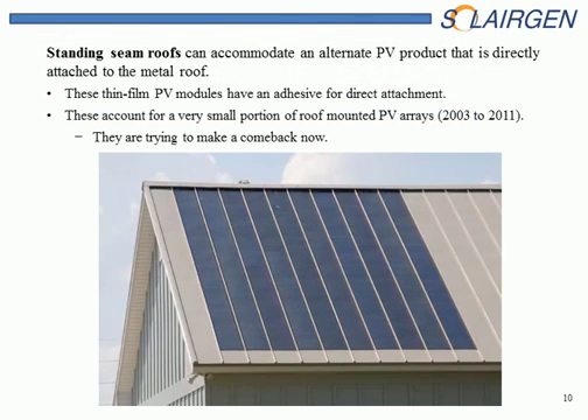An alternative method of installing PV modules on a roof requires an alternative manufacturing process for the PV modules. This is a thin film application. The ones we're looking at here are actually amorphous silicon, non-crystalline, but now they're making them out of another material called CIGS. It's basically a thin film application that's applied over stainless steel with a high temperature polymer coating on it, and there's an adhesive on the back side so it sticks to the metal roof. You won't see very many of these, but there are some in the state of Georgia. 2003 to 2011 is when this was primarily done in the state. There are some products coming on the market now, but like I said before, the likelihood of seeing this is pretty low.